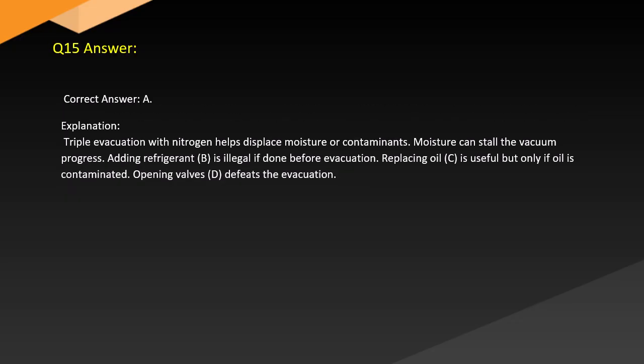Answer. Correct answer: A. Explanation. Triple evacuation with nitrogen helps displace moisture or contaminants. Moisture can stall the vacuum progress. Adding refrigerant, B, is illegal if done before evacuation. Replacing oil, C, is useful, but only if the oil is contaminated. Opening valves, D, defeats the evacuation.